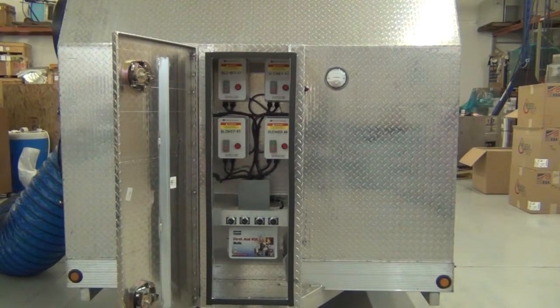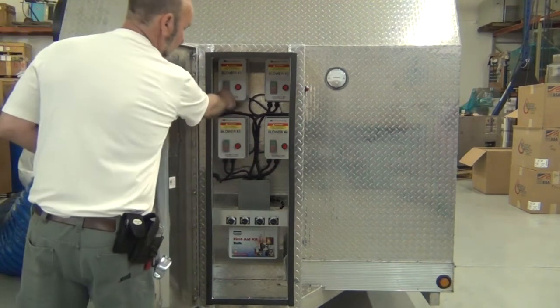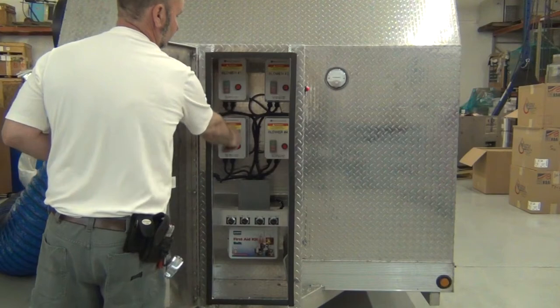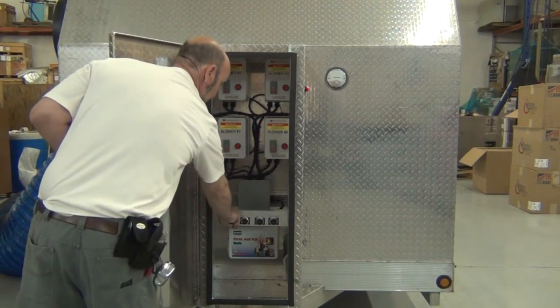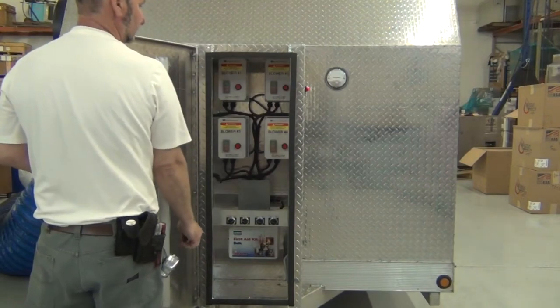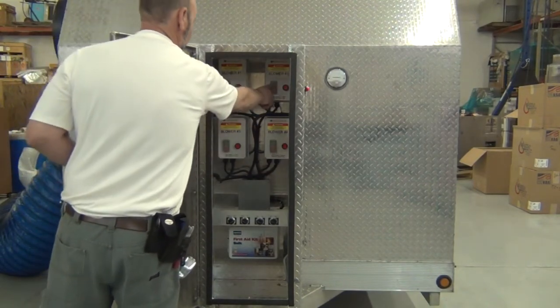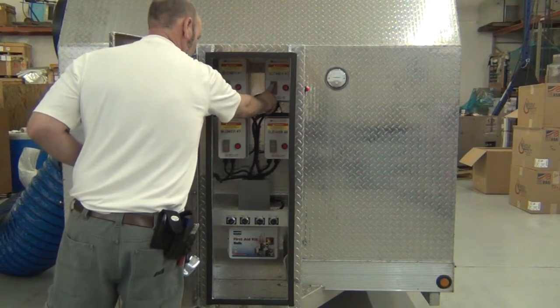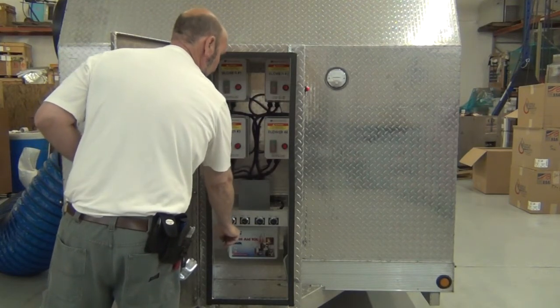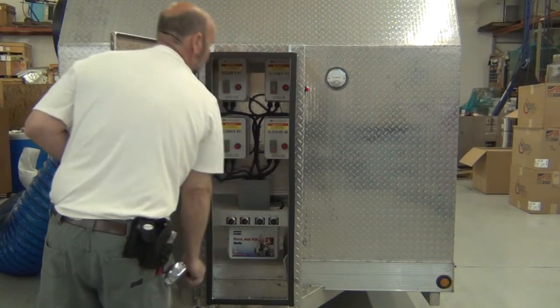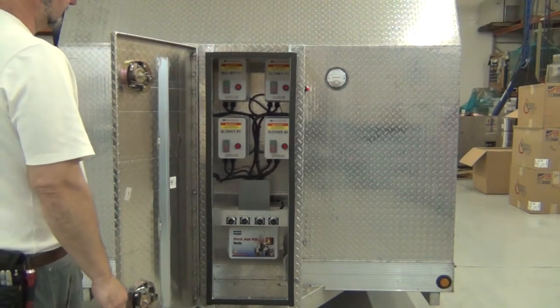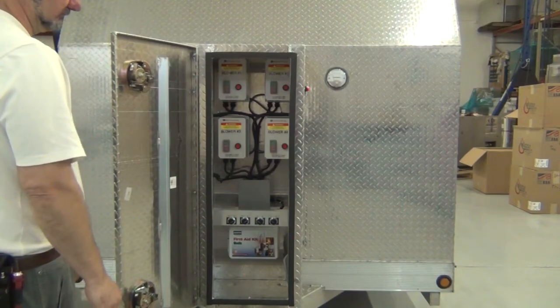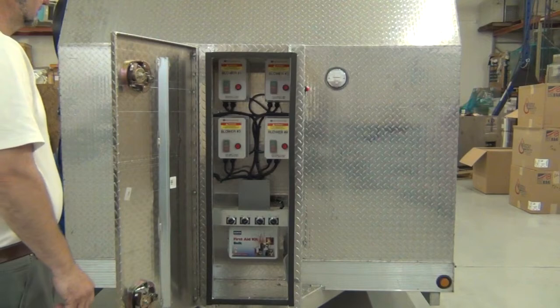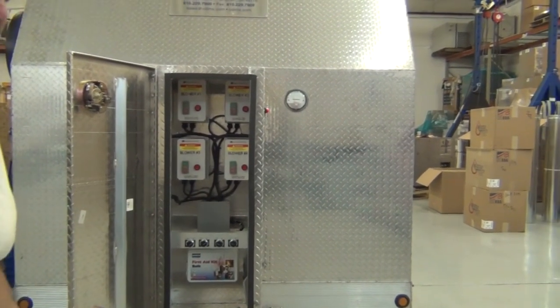So now with our 30-amp circuit power connected to blower circuit 1 and 2, we can go ahead and energize the blower systems by first pressing the green start button to allow power to the circuit, then turning the on-off switch to on. That will start the blower system circulating. Then we can go ahead and start blower system number 2. After a suitable time delay, go ahead and turn the switch to on. This will start both blower systems, so now we're circulating approximately 8,000 to 10,000 CFM through the HEPA filter banks.